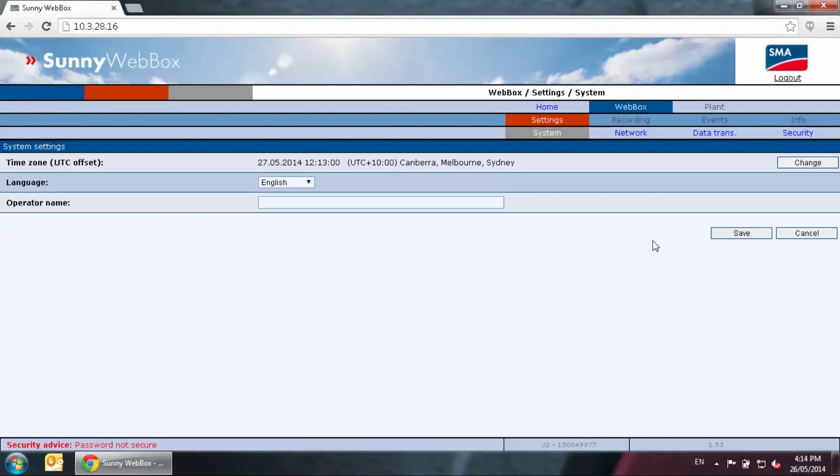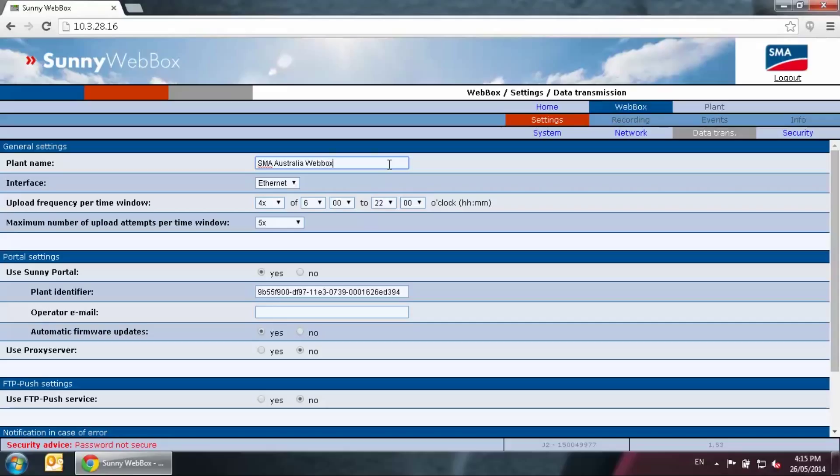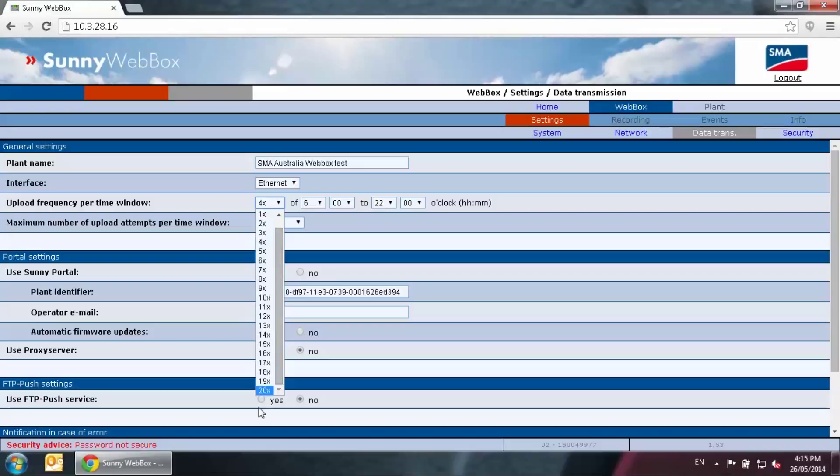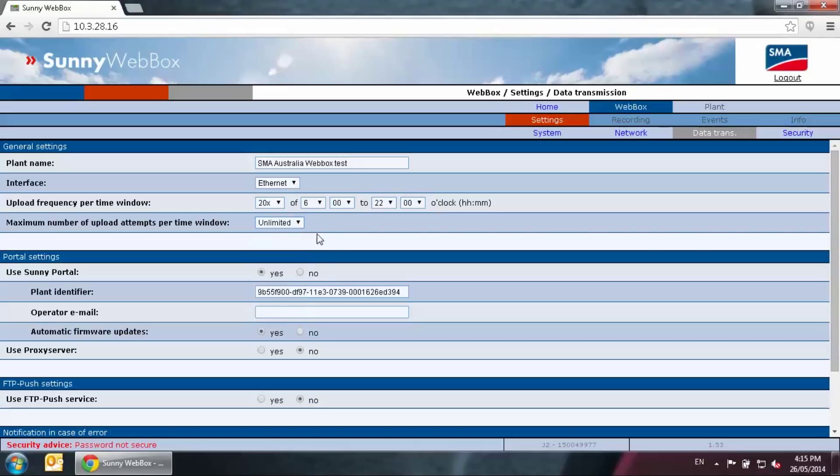Secondly, go to the web box tab and then data transfer. In here, the plant name is the Sunny Portal plant name that you wanted to show. You can always change this plant name at a later stage via Sunny Portal. Here we will just do SMA Australia web box tests. Upload frequency is how often the web box will upload data to Sunny Portal. You can change this to 20 times between the certain time period. You would like to set the maximum upload attempts to unlimited as well.